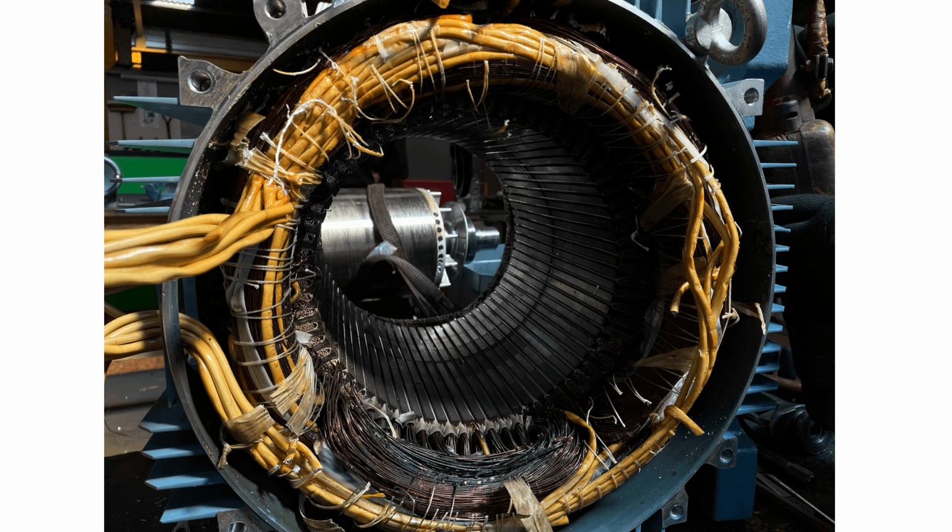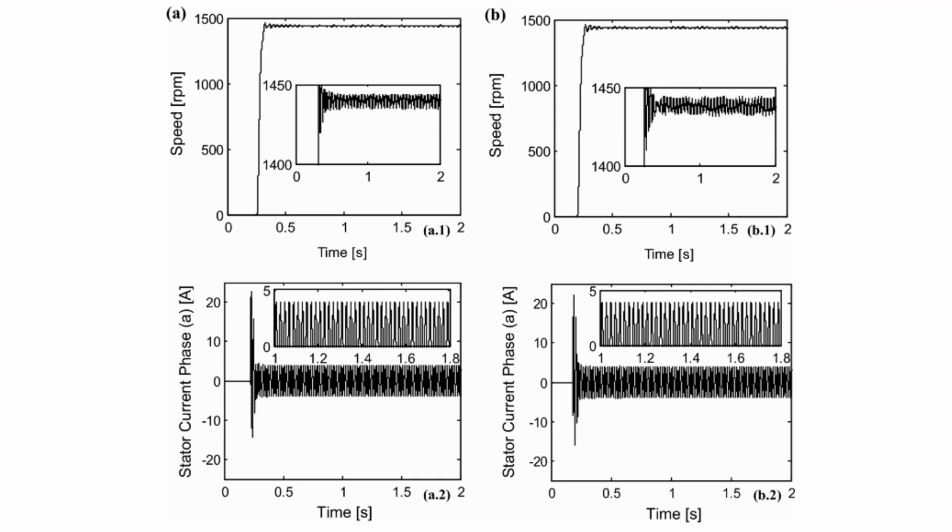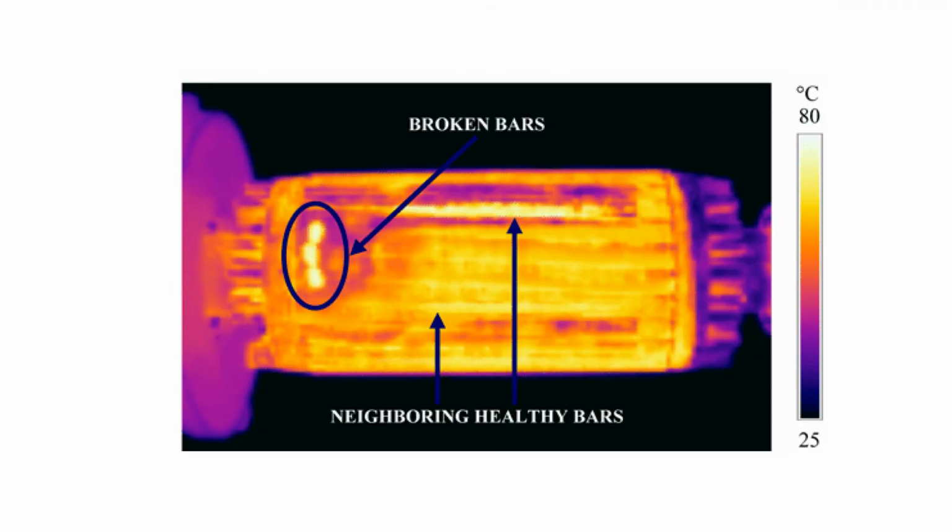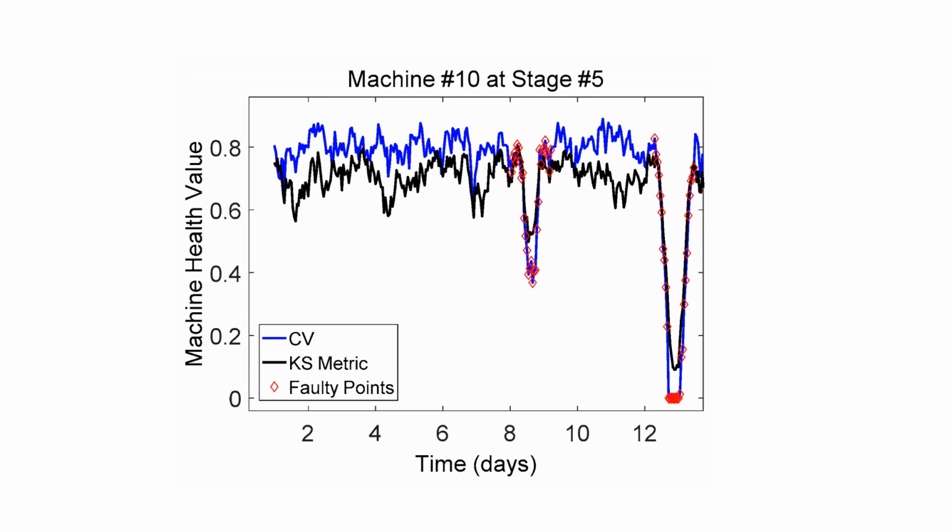Simulation allows us to compare the healthy condition with faulty conditions. For example, an inter-turn short circuit in a winding of a stator changes current distribution, magnetic flux, and torque ripple. These differences appear clearly in the simulated results, helping us to understand what to look for during monitoring.